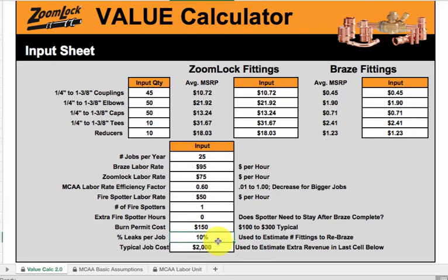Here's an MCAA labor efficiency rate, which is 0.6. MCAA comes out of their book at 1.0 — if you're not familiar with that, look on our website to explain that further. A fire spotter, which you're going to need most likely depending on your jurisdiction, and they show it at $50 an hour. That's required when you're brazing because you've got an open flame. And then your burn permit cost. They're assuming a 10 percent leak rate — one out of 10 of your brazed joints leaks — which you can change. That's pretty horrible; I would think it was much lower than that.